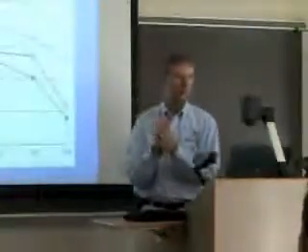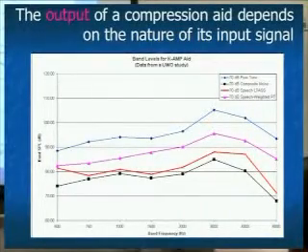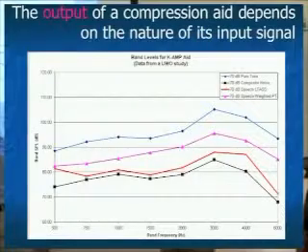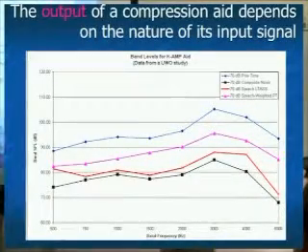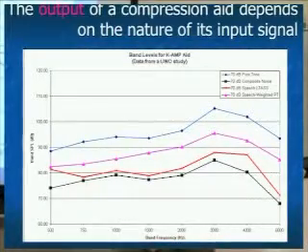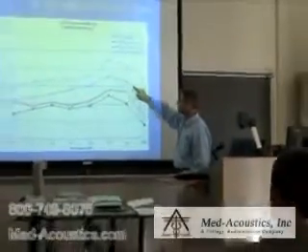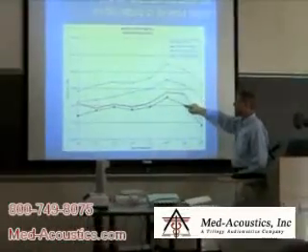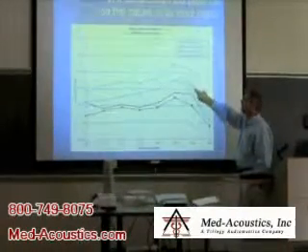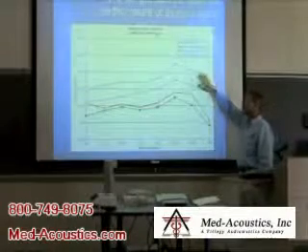Look at these output curves - you can measure two kinds of curves: gain and output. This is the actual output, so the scale goes from 60 to 120 dB SPL, measuring the output of the hearing aid in the ear. These four curves all have the hearing aid set the same, with the same intensity signal at 70 dB, but using four different types of signals.